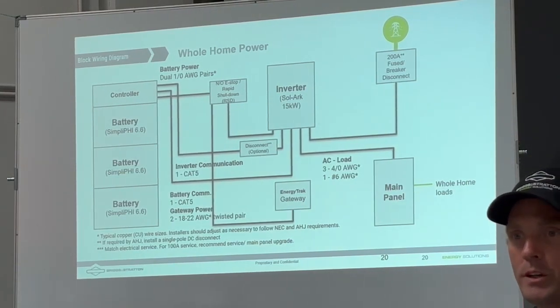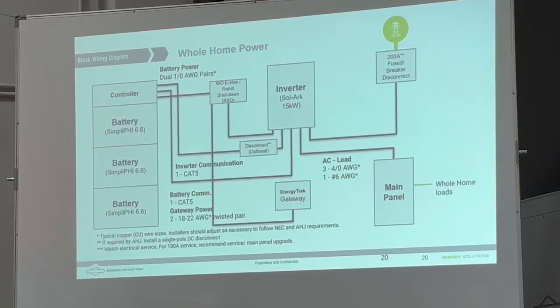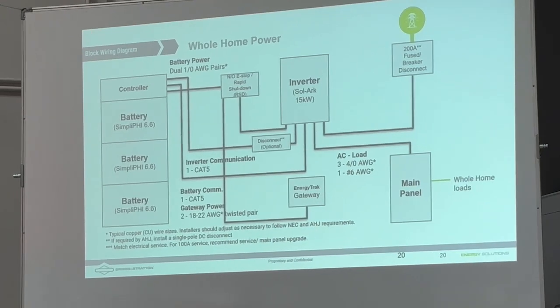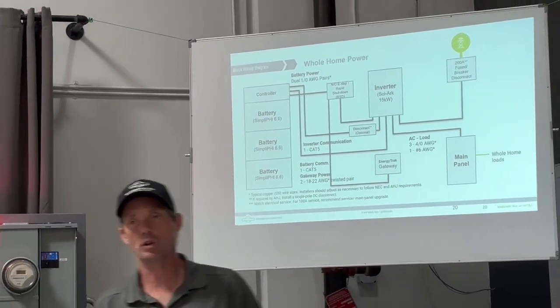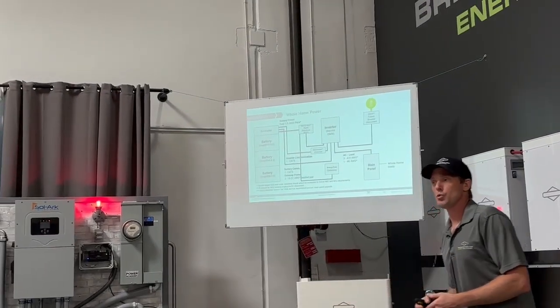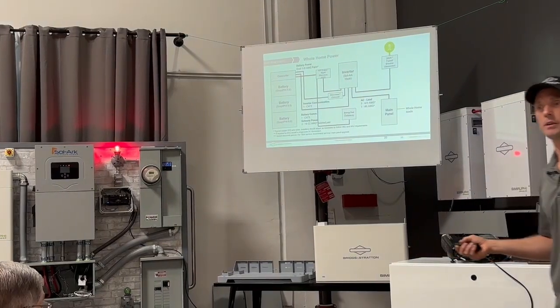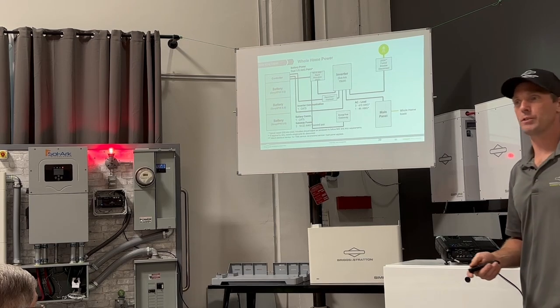Now, I don't want to ignore the fact that there are a lot of combo units in California, right? So you've got your service entrance here, but you might have your load center attached to that. What could be your option for that? Well, one of the things you could do is if you have a combo unit, you could feed the Sol-Ark 15K out of two 100 amp breakers on that combo unit, and then you still would have to install another load center. But that allows you to kind of retrofit a combo unit without having to change out your whole service entrance.